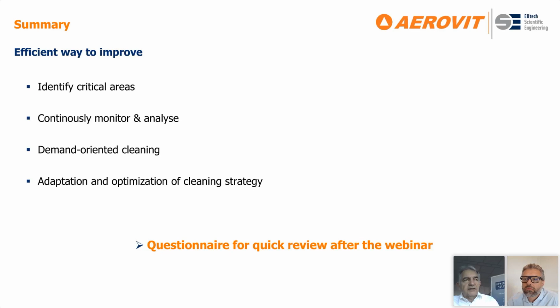On the other side, there's the artificial intelligence, adapted to your specific boiler, done automatically. We teach the system over time, taking images for a starting period, and train it by telling it, based on available information, what is severe and what is not. Then it runs very automatically and improves the algorithm itself. This is connected both to the cleaning device and to the DCS system to alarm the operators.